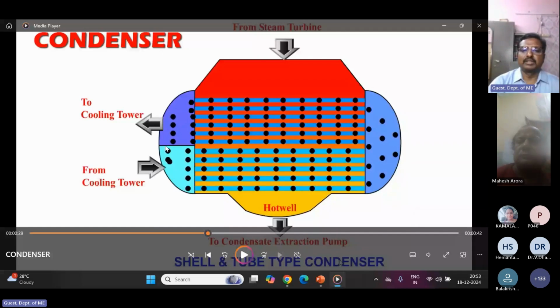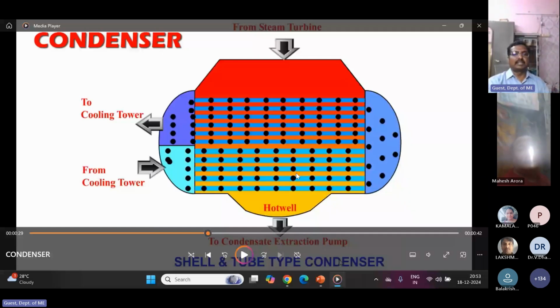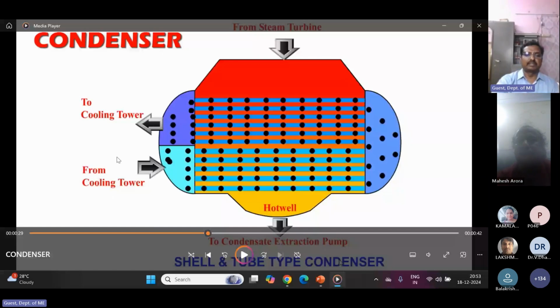So water comes from the cooling tower. Cooling tower technology is used, and there are some thermal power plants without cooling towers also. In our power plant, all six units are without cooling tower, because these are called once-through systems. Once-through system means there is no cooling tower. The water is taken from the river. Here we have one pump house at Bhavanipuram. From Bhavanipuram, from the Krishna river, they take the water and supply it to the power plant.